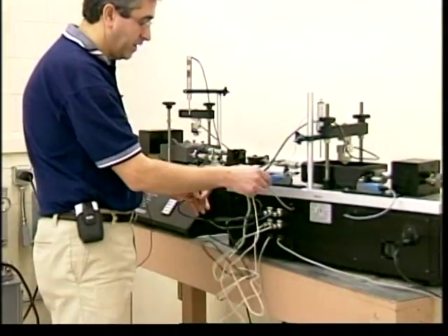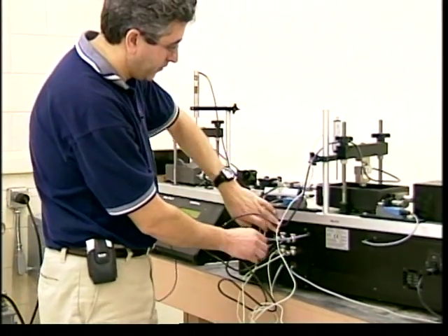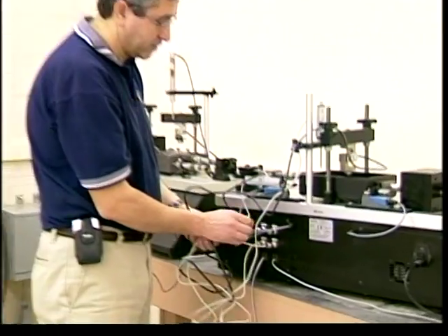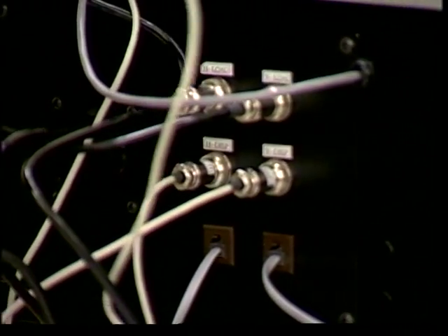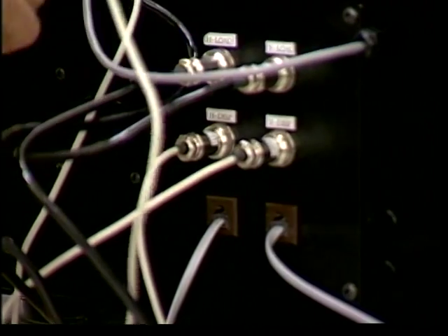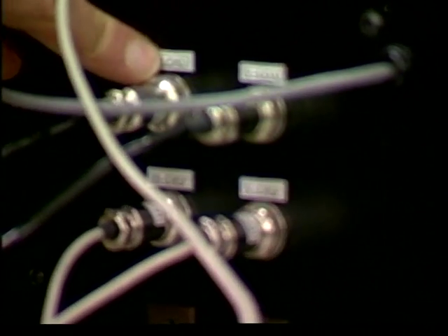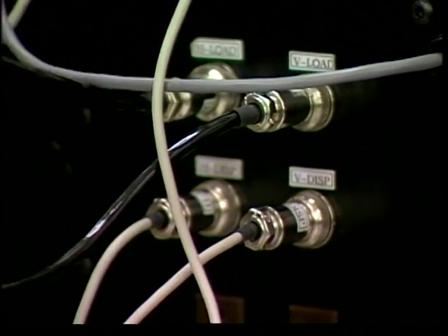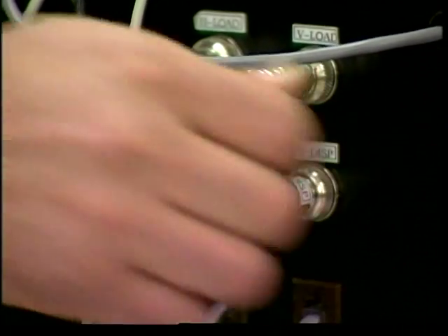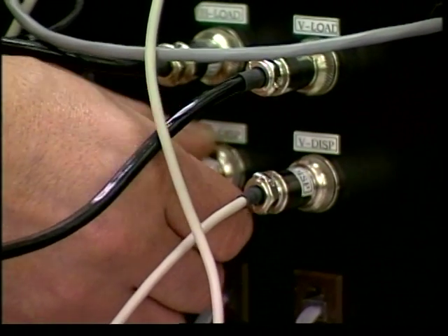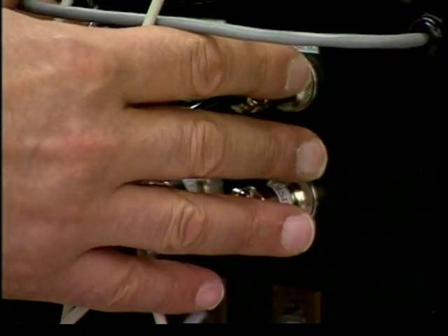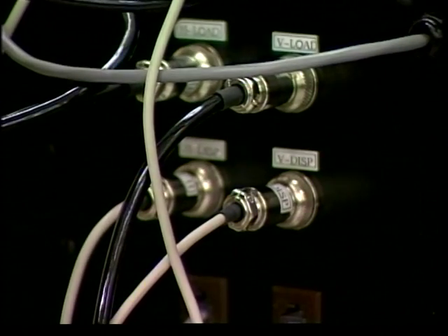And if you look at the back here, you have the vertical side and a horizontal side. So the vertical load cell is connected. This is your vertical load cell. If you trace it back here, it is connected to the top, labeled V load. Same thing with the horizontal load. This is your horizontal load, your vertical displacement sensor, and your horizontal displacement sensor. Those are the 4 connections for the 4 sensors.